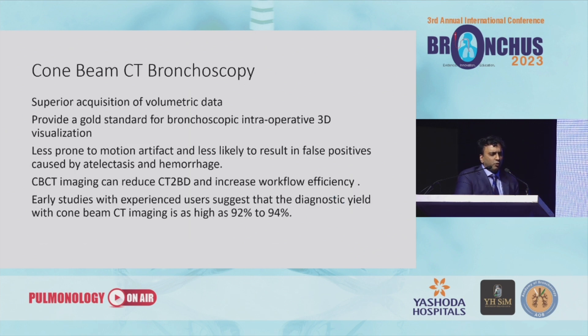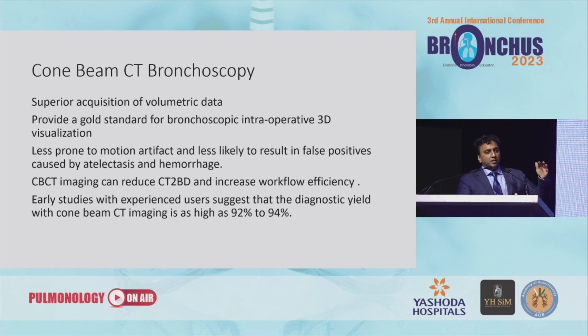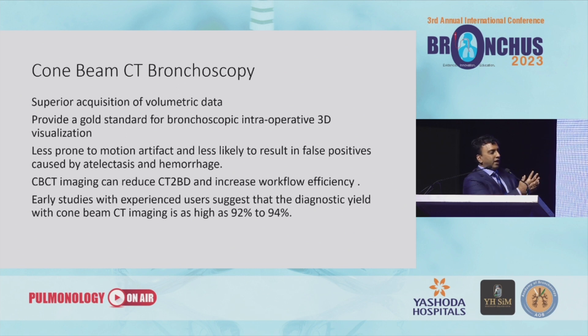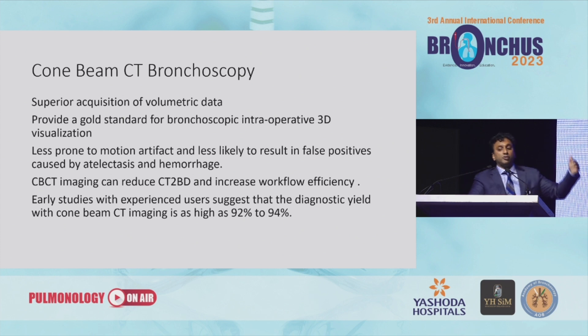Digital tomosynthesis is kind of 2D-and-a-half — it's not quite applicable to every single lung nodule. Currently, the gold standard is cone beam CT bronchoscopy. With digital tomosynthesis you're stacking 2D images, whereas cone beam uses a cone of radiation to a flat panel detector that spins 270 degrees around the patient, creating images comparable to a multi-detector CT scan. It's less prone to motion artifact with a spin in 5 to 8 seconds, and early users are seeing diagnostic yields of 92% to 94%.